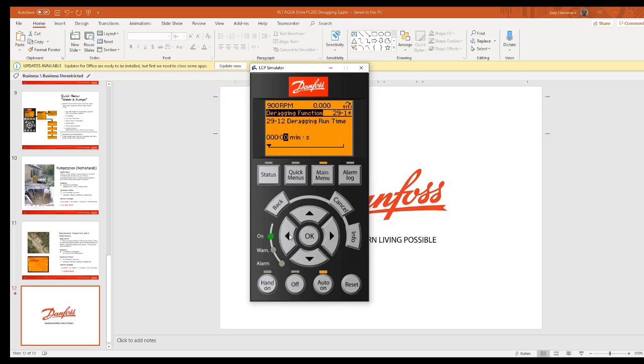How long do I want it to run? Let's say 30 seconds forward and reverse with an off delay of 10 seconds in between, and what speed? So let's say about minimum speed. And this gets pushed up to minimum motor speed, the lowest this can be set. And that's it for the preventive. So just deragging at start. And there is a choice, start or at stop or both. But this is the simplest method here, and it's not a lot to set up.